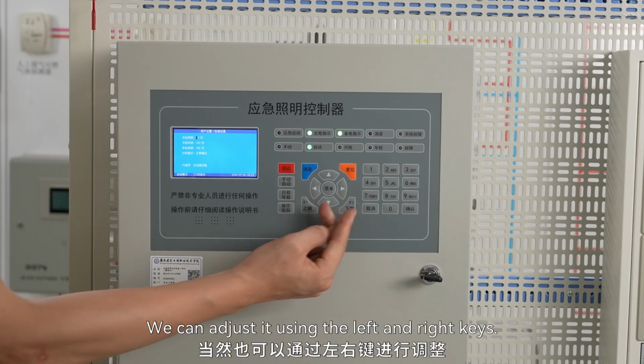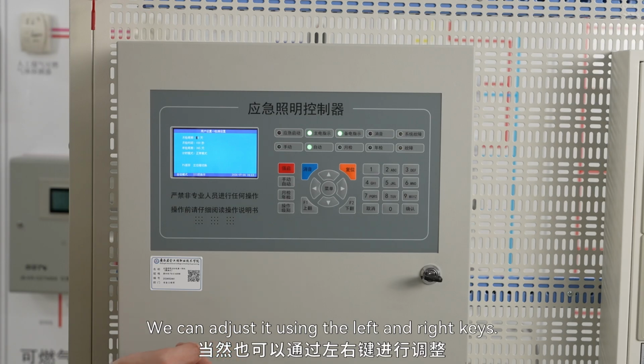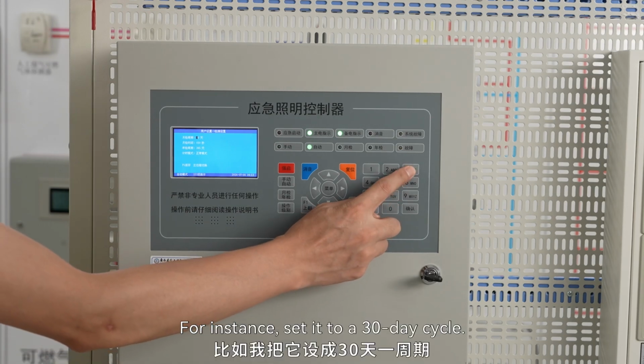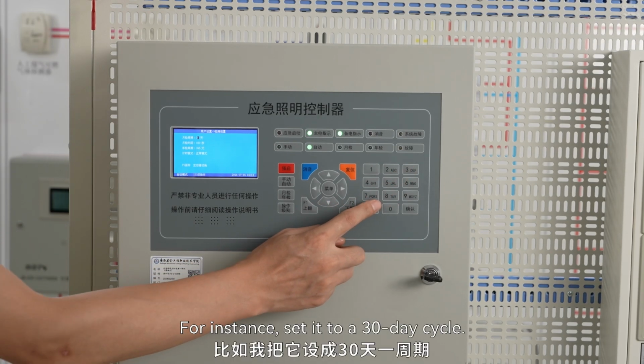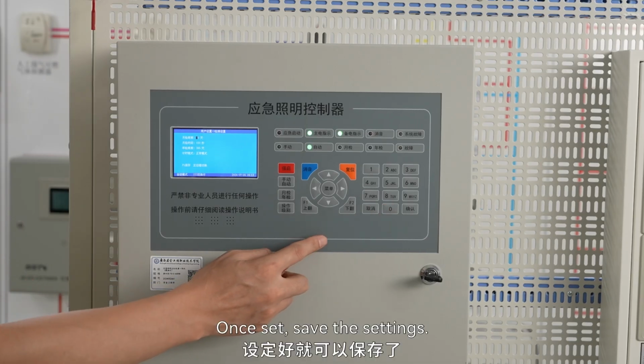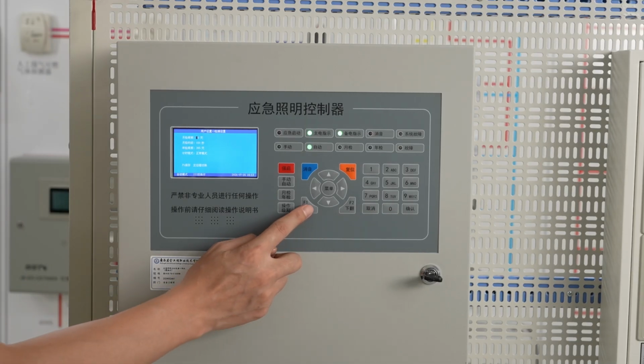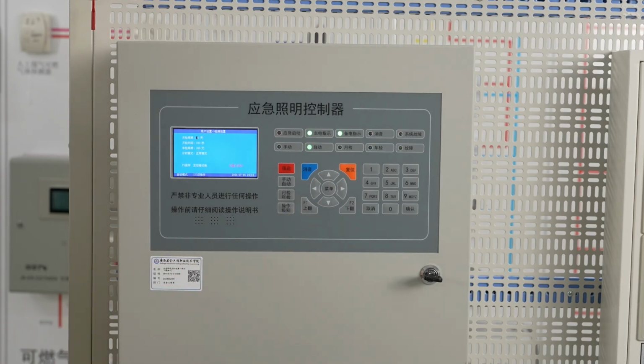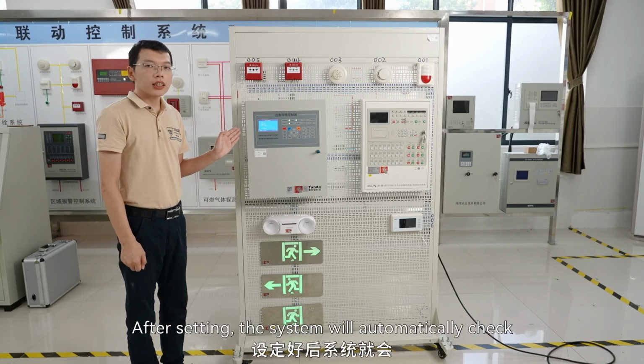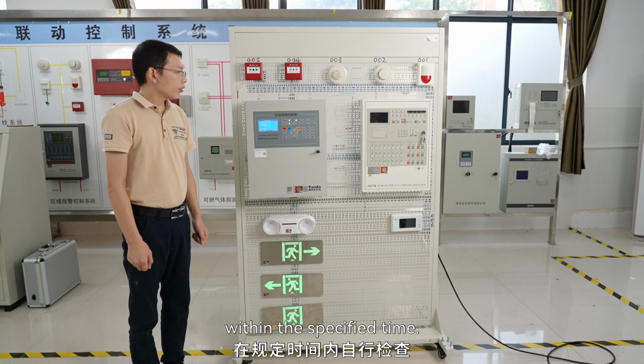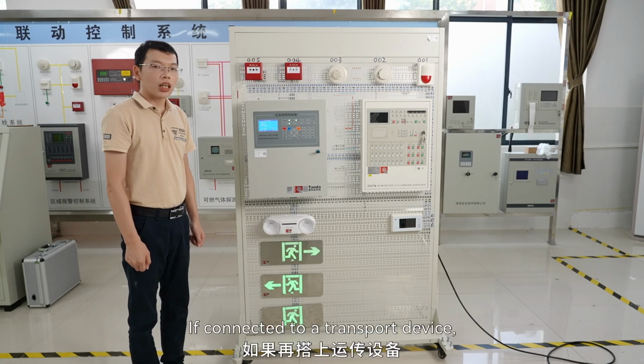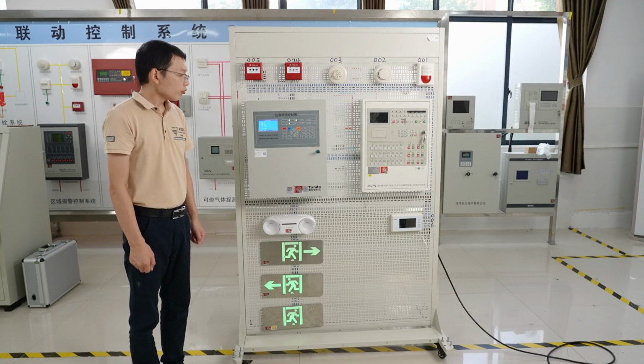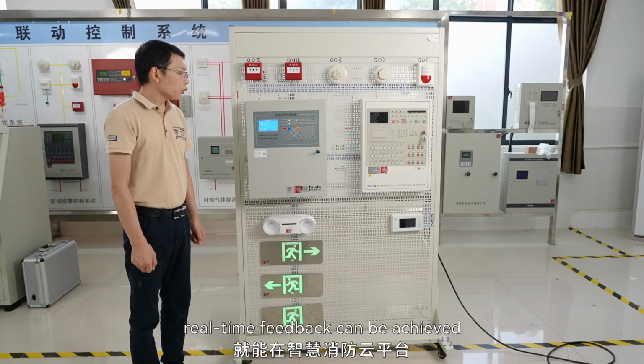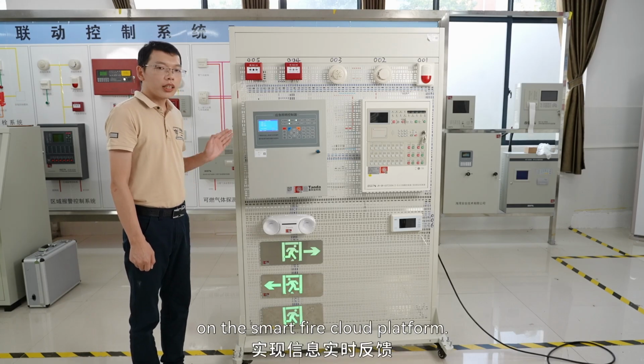We can adjust it using the left and right keys. For instance, set it to a 30-day cycle. Once set, save the settings. After setting, the system will automatically check within the specified time. If connected to a transport device, real-time feedback can be achieved on the Smart Fire Cloud platform.